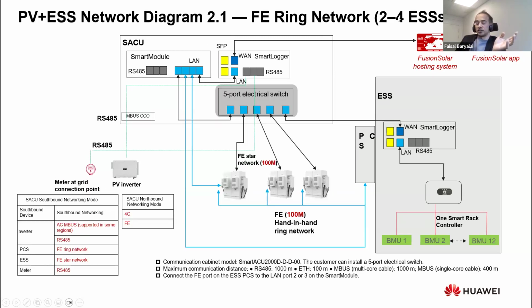But let's say when there are more ESS, more cabinets connected in parallel, for instance from 2 to 4 ESS, then we still have SACU, but keep in mind that you don't need SACU itself. You could use just the smart logger and smart module, but you need a 5-port switch, this extension switch. Then the PCSs are connected in between each other in the cabinet, and the first and the last PCS are connected to the LAN port of the smart module. So this is a star and ring communication system. Still, we need to connect every CMU sitting inside the ESS to the 5-port switch as before.